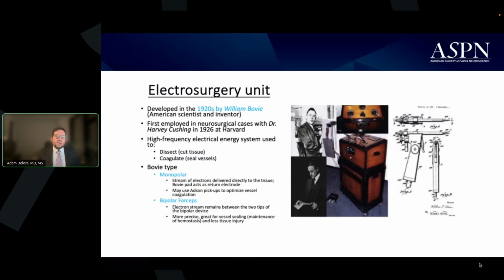So there's two different types of Bovies. One is a monopolar Bovie, which is a pencil-like device where you'll have a grounding pad and the pencil, and the high frequency electrical current will go from the Bovie, and you can go ahead and gain hemostasis in tissues, and then it'll go to the grounding pad, which will be placed on an area of the patient without any metal in it. There's also bipolar forceps, where the electrical current goes in between the two tips of the device. So it can be used for vessel sealing and different things like that.